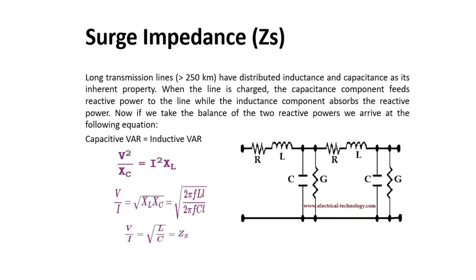So the 2 pi f terms cancel out, and we are only left with L and C. The square root of L divided by C is our surge impedance Zs, and this is called the surge impedance. So if you know the inductance and capacitance of the transmission line, you can calculate the surge impedance by the square root of L by C. This quantity, which has the dimension of resistance, is known as the surge impedance of the line when a purely resistive load of equal value is connected with the transmission line.